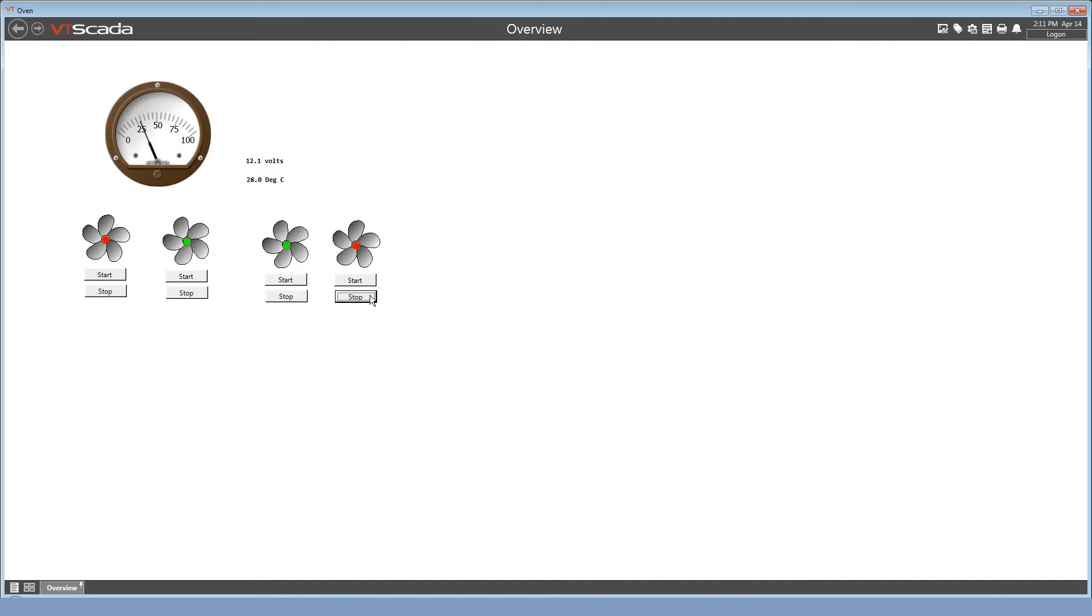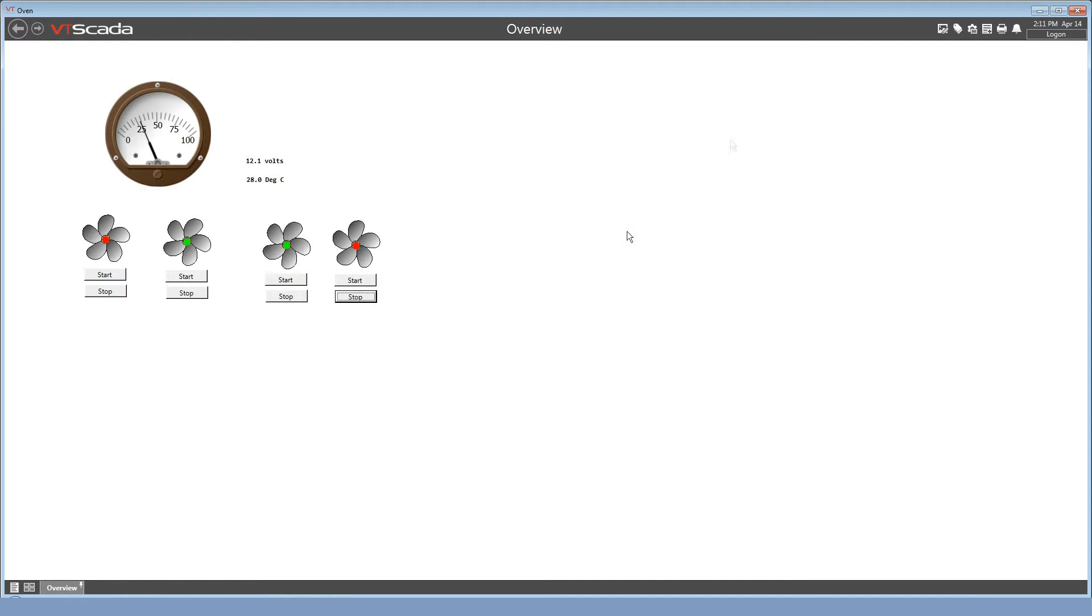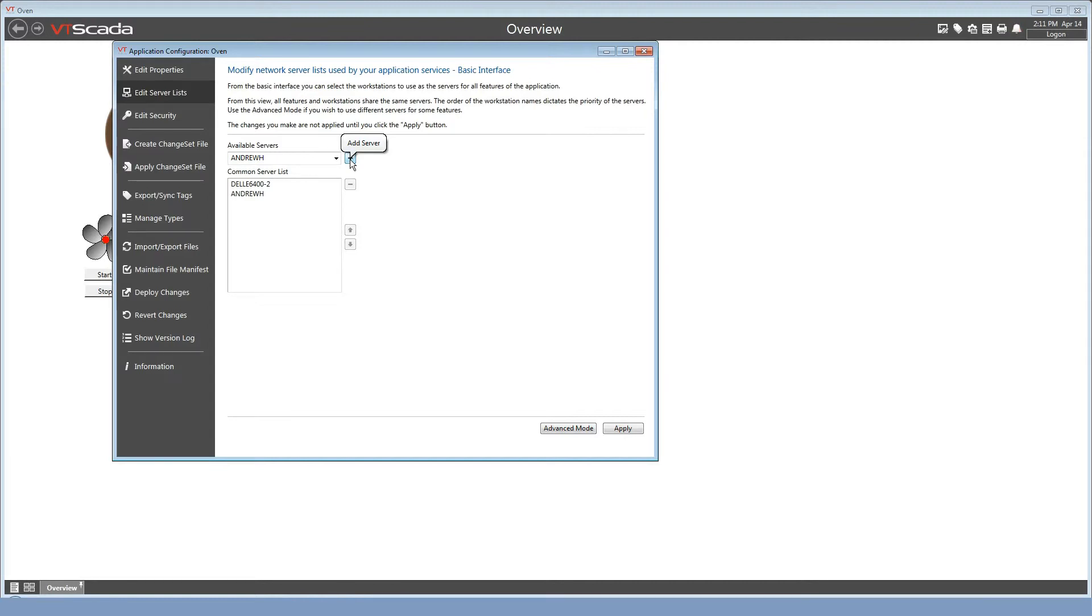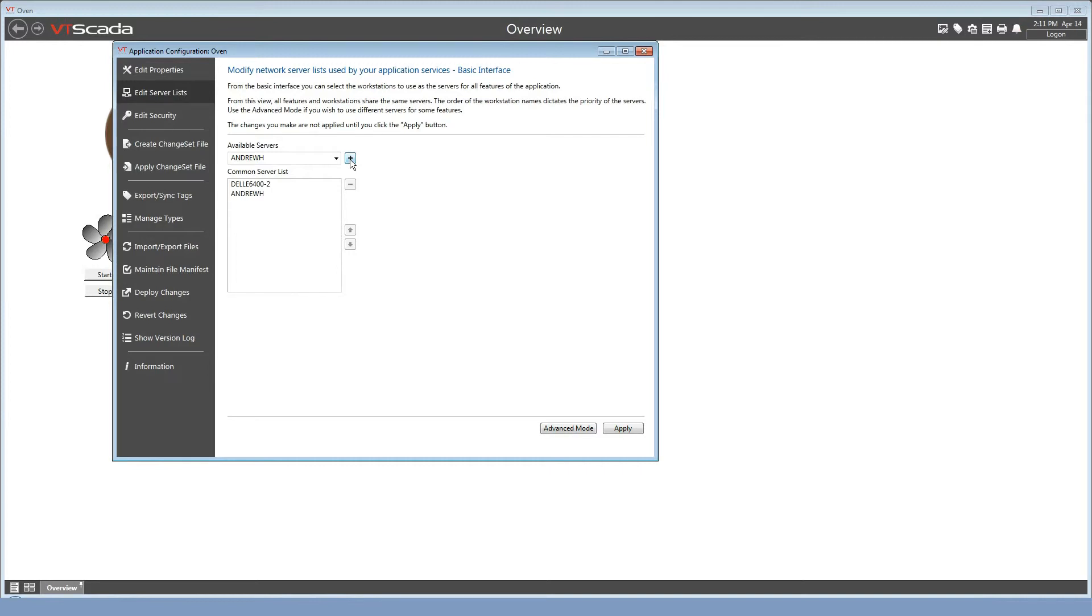Now to make this computer a backup server, I can open up its application configuration dialog. I'm going to put my computer name into the server list and click the plus sign. I'm able to do this even over here on this client computer because I'm running with an account that has configuration privileges, or actually security is not enabled, so I have full privileges. And any computer can be used for configuration just so long as that workstation isn't restricted by a runtime-only license.